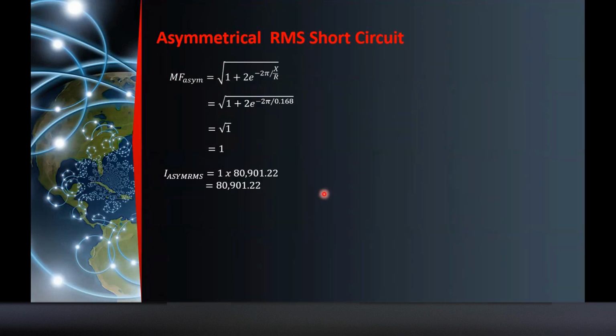So, pag nagsasize up pala tayo ng circuit breaker, tatandaan natin, hindi lang ampere frame na nakasanayan natin, dapat meron tayong interrupting capacity, meron tayong asymmetrical RMS short circuit ng breaker, at meron tayong peak current short circuit, tsaka short circuit power factor. Okay? So, marami pala, no? Hindi lang pala pag sinabi nating 2,000 ampere, ay ikabit mo yan 2,000 ampere, hindi na ako magko-compute, okay yan.